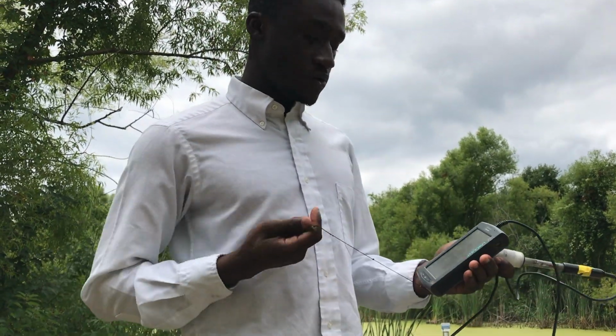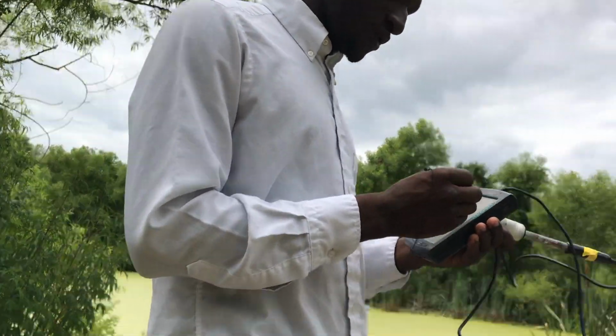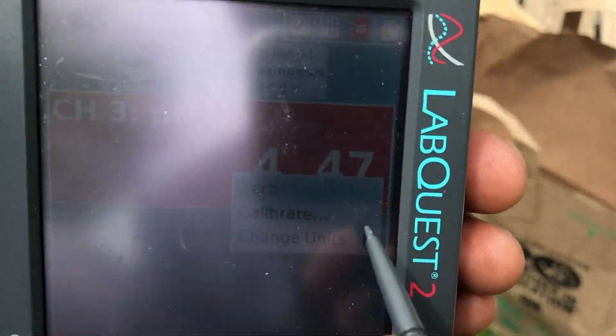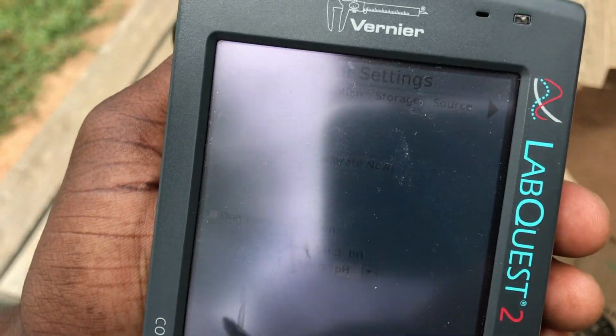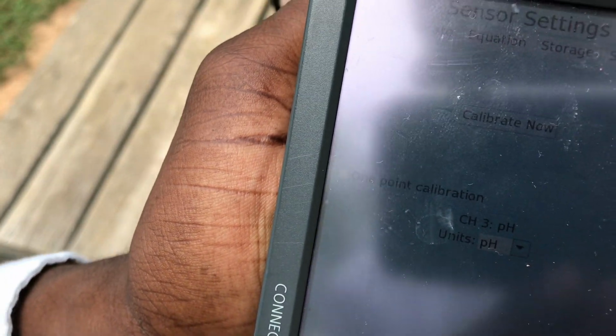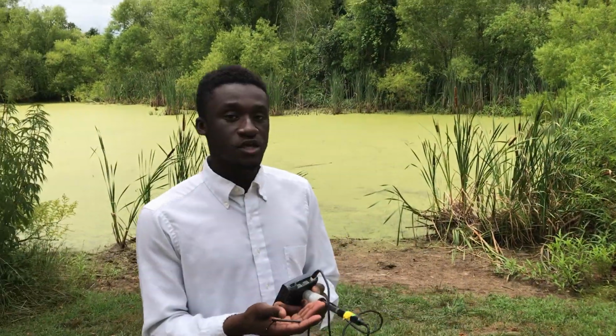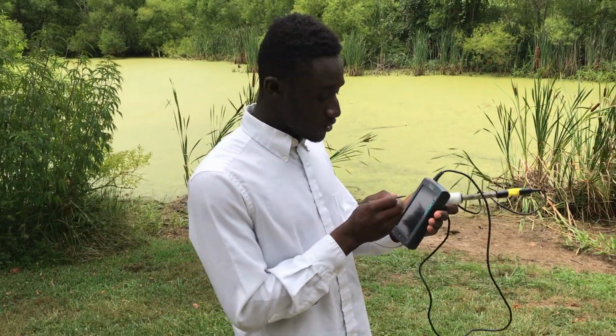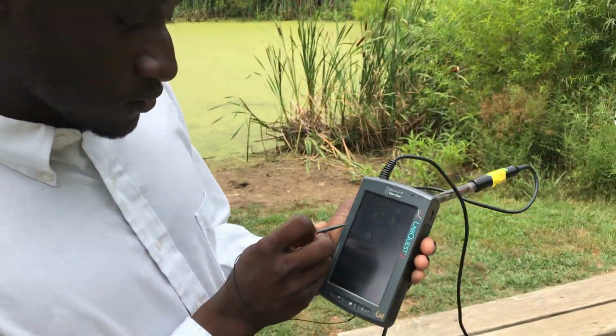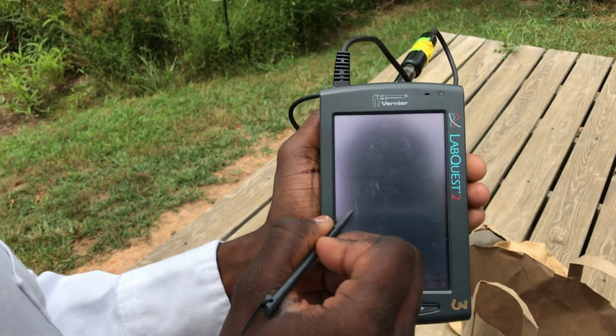So in order to do the 1-point calibration, we can go here on our screen where we're reading it out. We can tap it, we can go to calibrate, and we see there's a little button here for 1-point calibration. The automatic setting for LabQuest systems is to use 2-point calibration simply because it's more accurate. But a lot of times, for example, with the pH probe, that's simply not possible. So what we're going to do is click this little button here. It's very, very small. And then we're going to click OK.